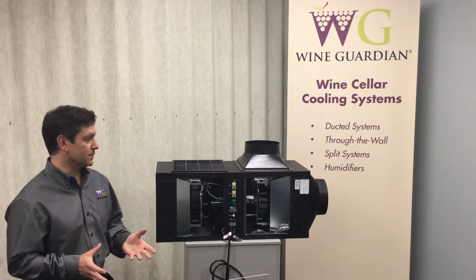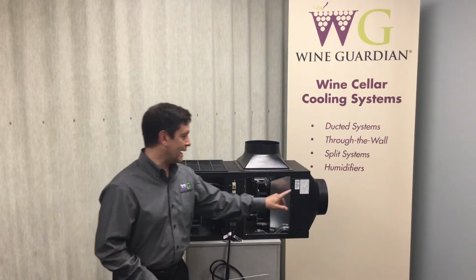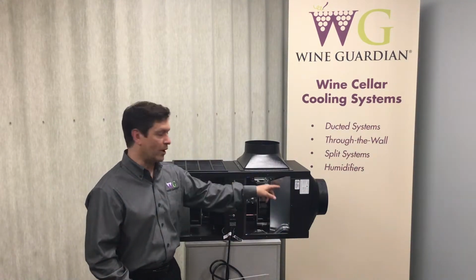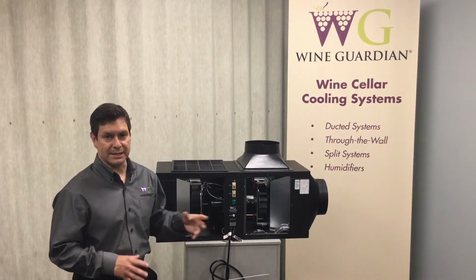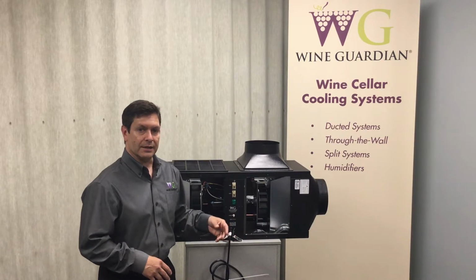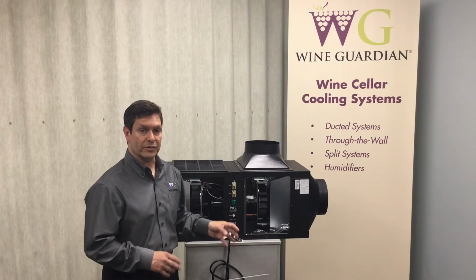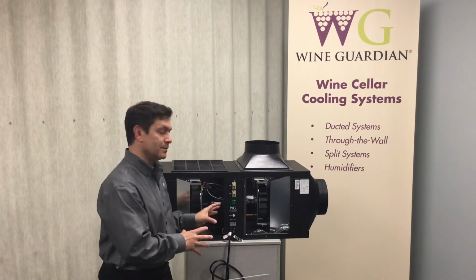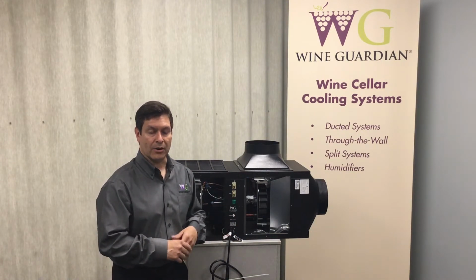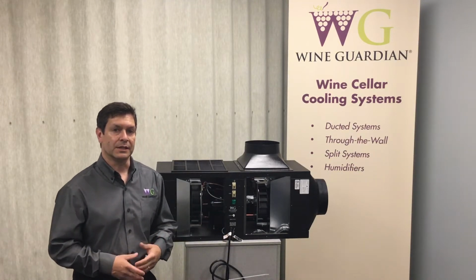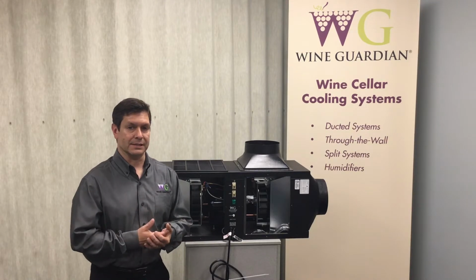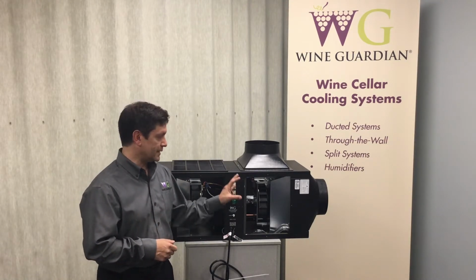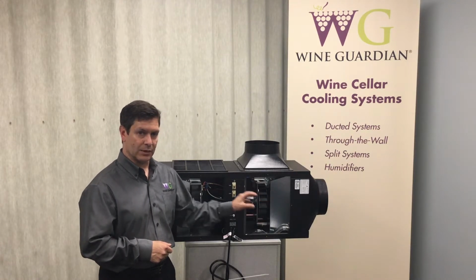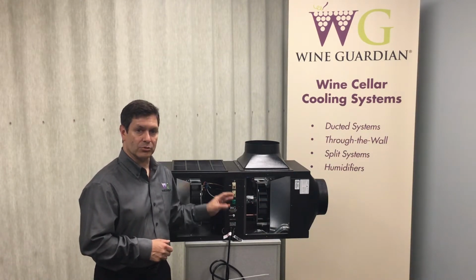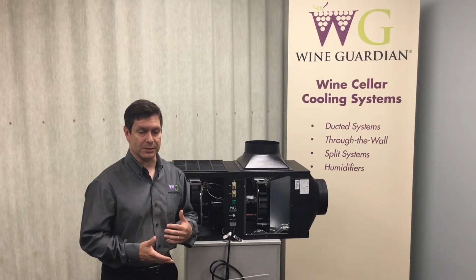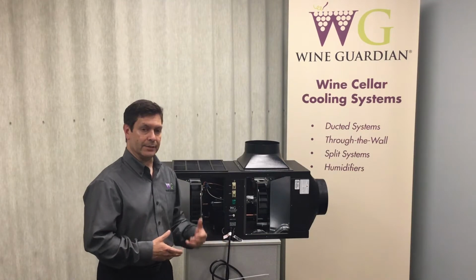So how it works is there is a sensor that's mounted on the coil face itself, and it's wired back to our control panel. What that sensor does is it monitors the temperature of the cooling coil. So if it gets too cold, it forces the system to stay off. Our controller allows for the setup of that function, but basically it has an initial set point of 35 degrees. So if that sensor sees the temperature at 35 degrees, it will keep the system off until it rises above 40 degrees Fahrenheit. Once it gets above 40 degrees Fahrenheit, the system turns back on and begins to cool again.